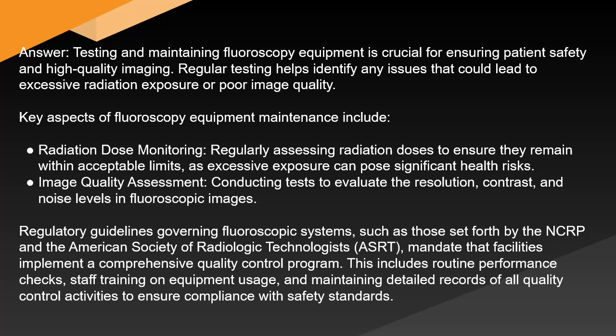Image quality assessment, conducting tests to evaluate the resolution, contrast, and noise levels in fluoroscopic images. Regulatory guidelines governing fluoroscopic systems, such as those set forth by the NCRP and the American Society of Radiologic Technologists (ASRT), mandate that facilities implement a comprehensive quality control program. This includes routine performance checks, staff training on equipment usage, and maintaining detailed records of all quality control activities to ensure compliance with safety standards.